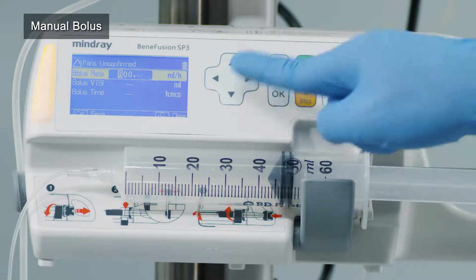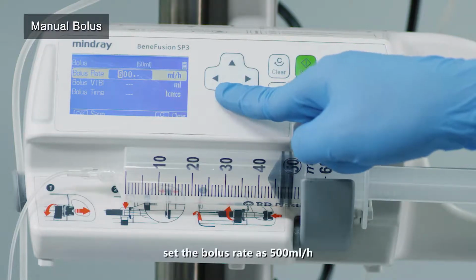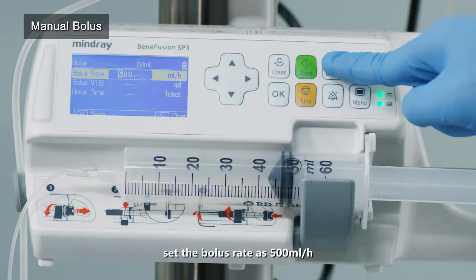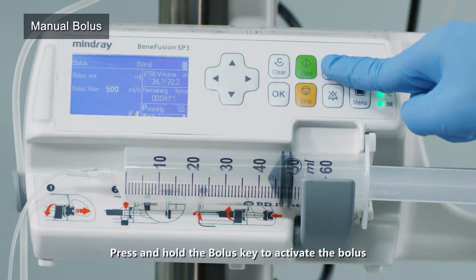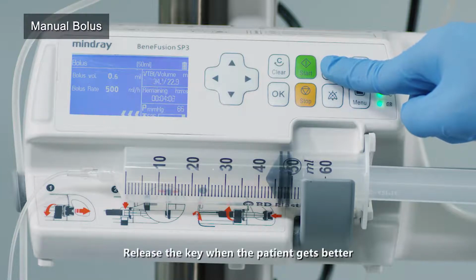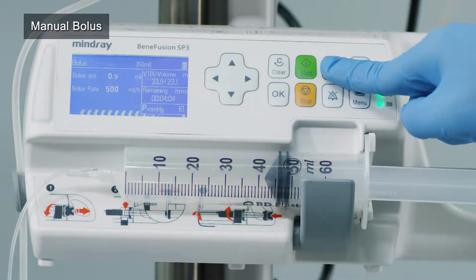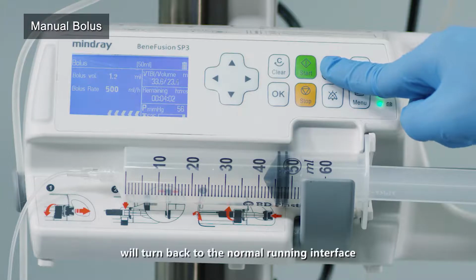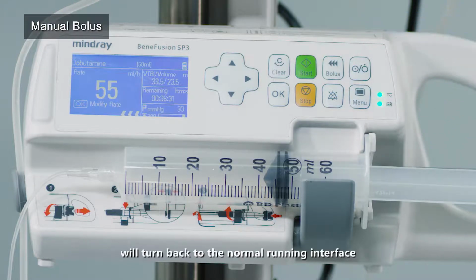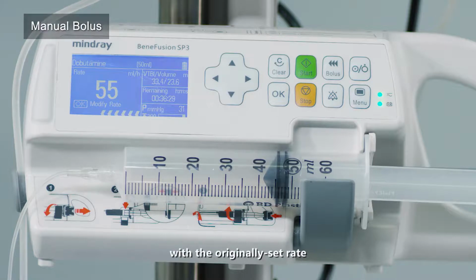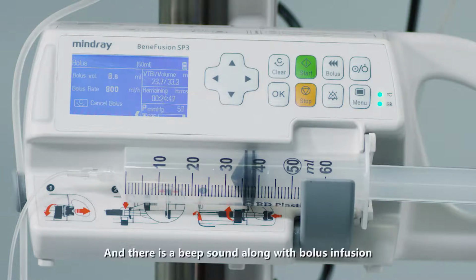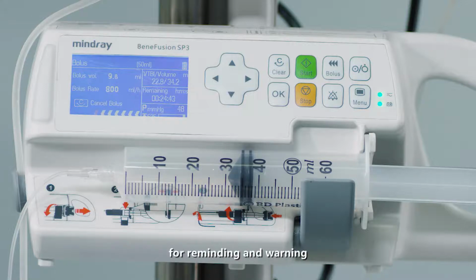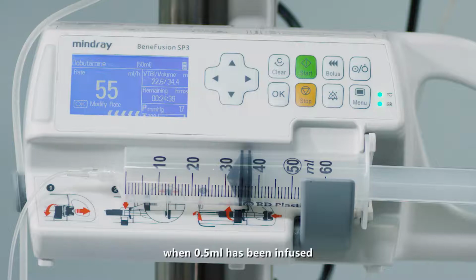For example, set the bolus rate at 500 milliliter per hour. Press and hold the bolus key to activate the bolus. Release the key when the patient gets better. Then the pump will turn back to the normal running interface with the originally set rate. And there is a beep sound along with bolus infusion for reminding and warning when 0.5 milliliter has been infused.